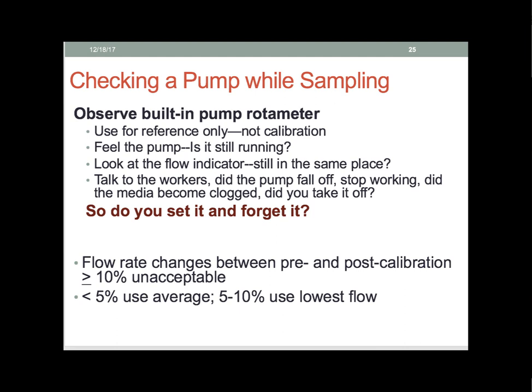While you're sampling, you can use your built-in rotometer to see where the pump is running as a reference point. You can feel the pump to make sure it's still running, and talk to your workers — if it became fouled, they can tell you. We need to do our pre and post calibration. If the difference between the pre and post is greater than 10%, it's considered unacceptable — throw it out or use the lowest flow. If it's between 5 and 10%, AIHA says use the lowest flow. If it's less than 5%, we can use the average.